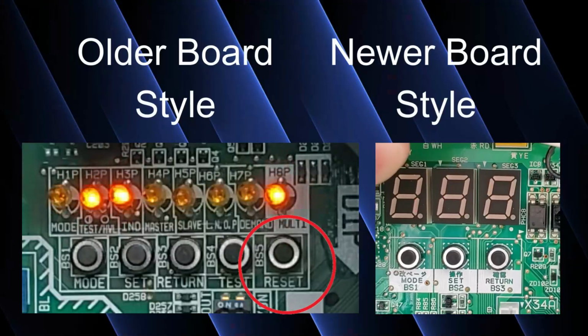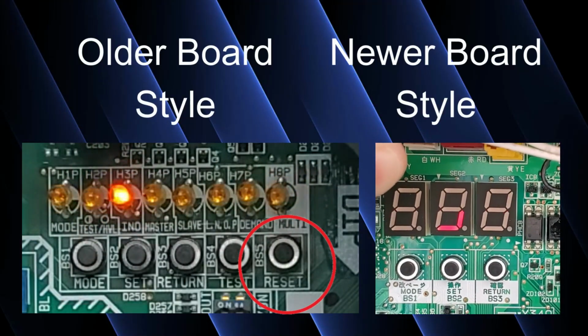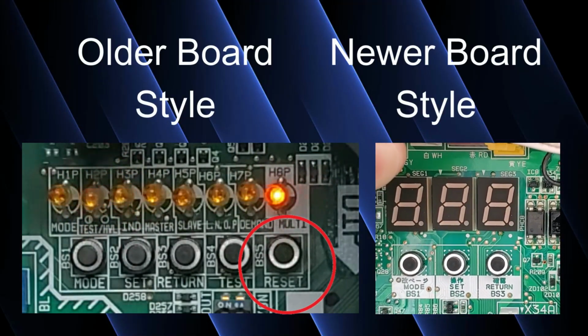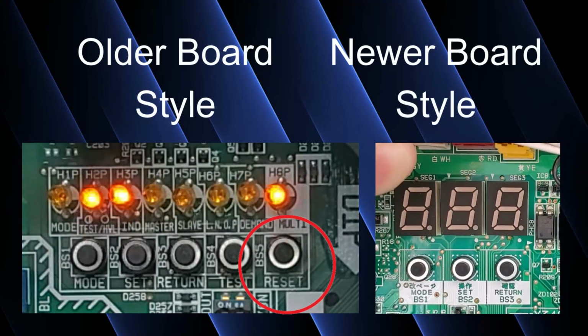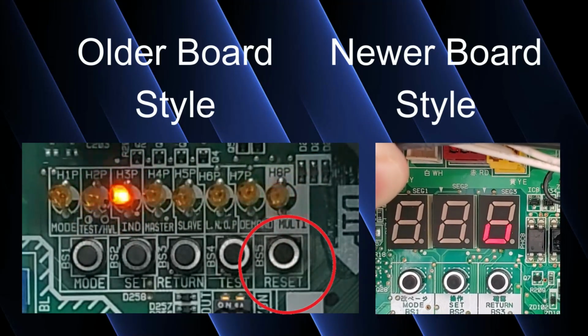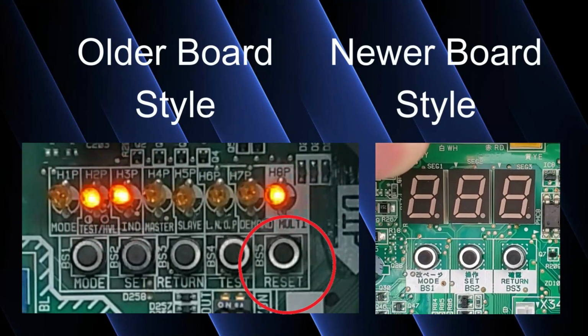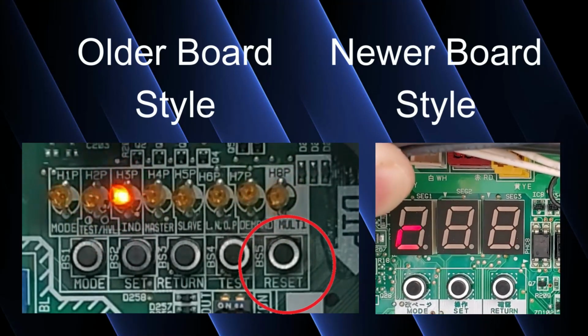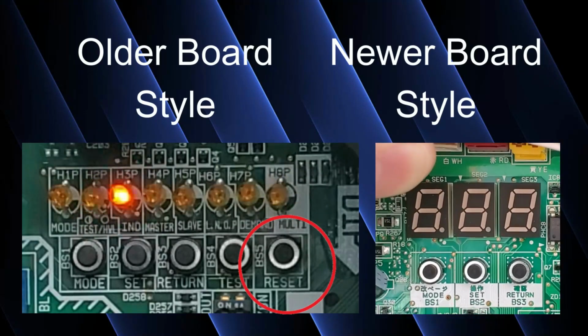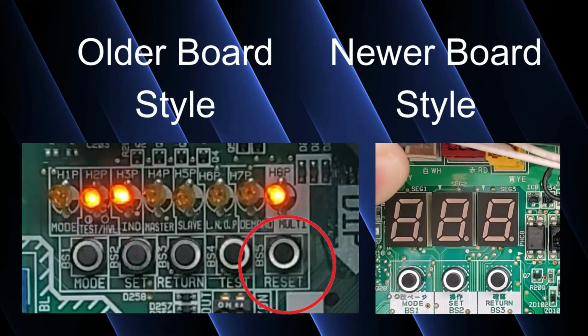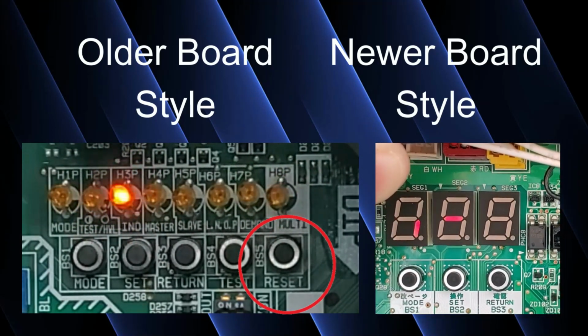outdoor unit. So you turn the disconnect on, clunk, walk over to the unit, you verify H2P is blinking, H3P is solid, you hold the reset button for 20 seconds. The reason you hold it for 20 seconds is because depending on what literature you actually read, some of the literature says to long press. Some of the literature will actually give you an amount of time to press, but it always seems inaccurate. So what I have found over the years is if you press and hold reset for 20 seconds and then let go, it will work basically every single time. It works every time for me, at least.